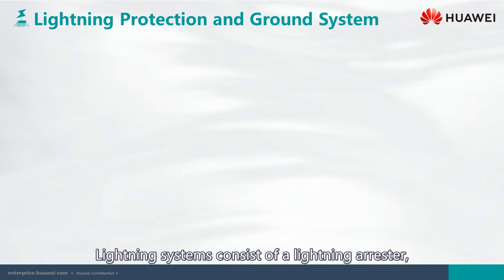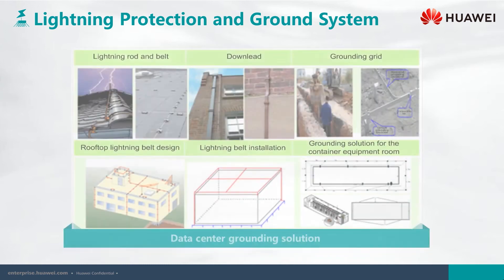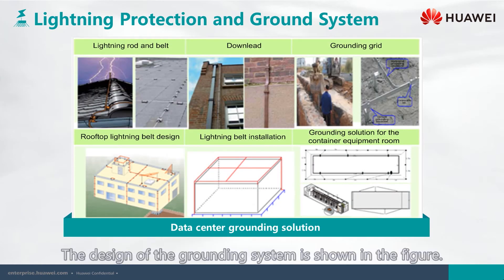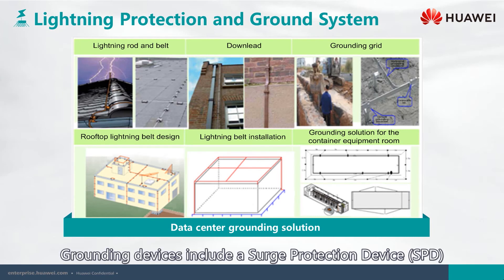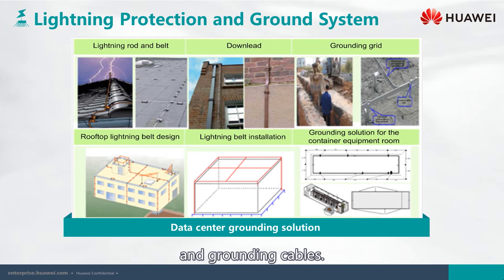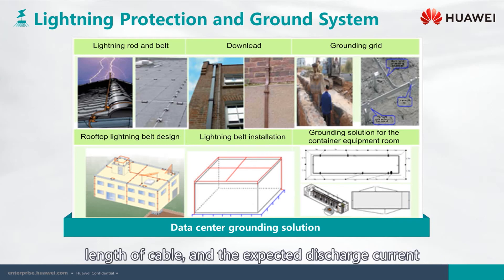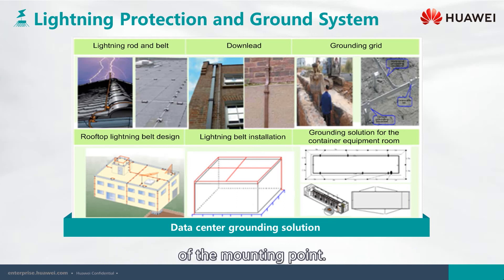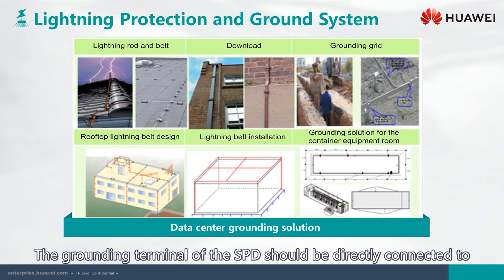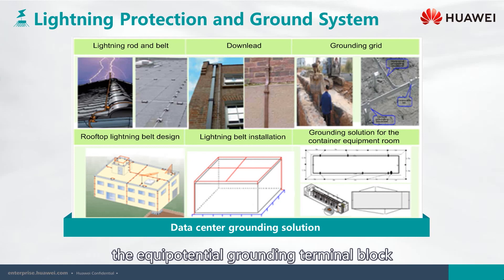Lightning systems consist of a lightning arrestor, down lead, and grounding devices. The design of the grounding system is shown in the figure. Grounding devices include a surge protection device (SPD) and grounding cables. The SPD's setting should consider the protection distance, length of cable, and the expected discharge current of the mounting point. The grounding terminal of the SPD should be directly connected to the equipotential grounding terminal block of the lightning protection zone at the shortest possible distance.